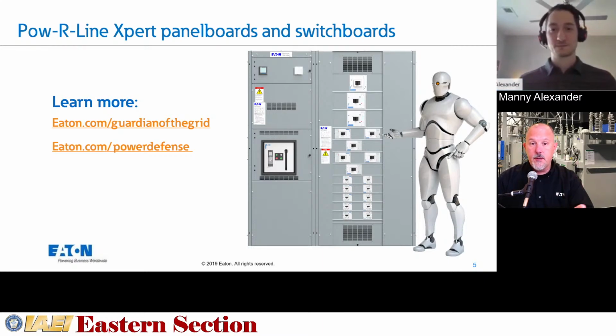From a testing standpoint of the arc reduction maintenance switch, there is a feature that you can use with the breaker that you can put into test mode and test that. That would be almost like secondary current injection testing. But if you think about the requirements of 240.87 and 240.67, it's 1200 amps and above. GFPE is required at 1000 amps and above, and you're required as part of 230.95 to test ground fault protection of equipment via primary current injection testing.